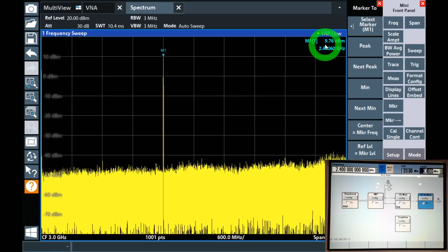So first thing is let's reduce the power. Let's go down to 10 dBm. And let's go into the baseband generator here, into the arbitrary waveform generator. And I've already configured it. Let's go into multi-carrier. So you can see that I have set carrier spacing of 5 megahertz, and I've created 2 carriers. So this is going to be a two-tone signal. If I go under the carrier table here, you can see that we have 2 tones. Both of them are enabled, plus 2.5 and minus 2.5 megahertz around the carrier. So we can go ahead and download that into the instrument, create and load.